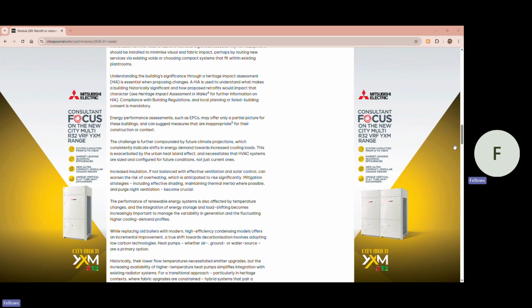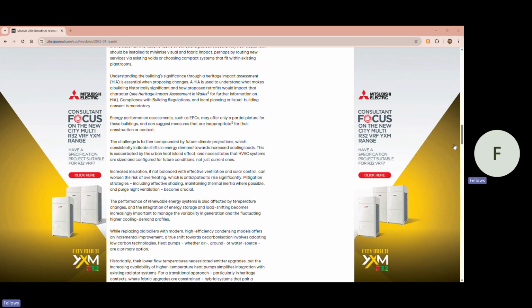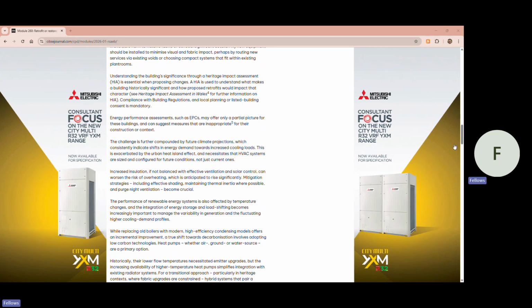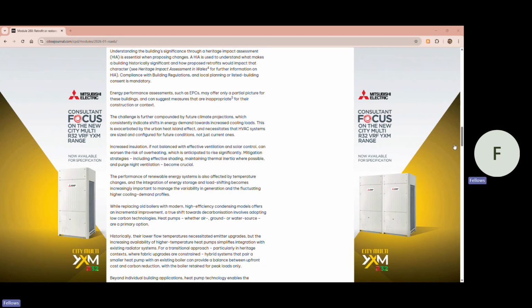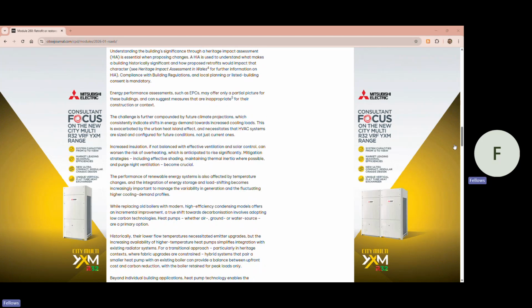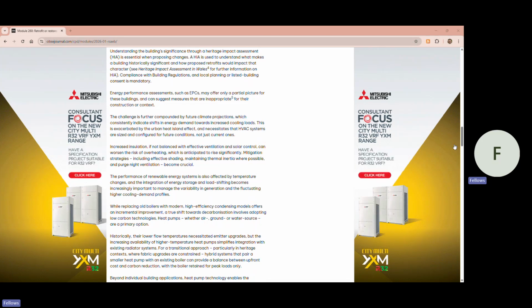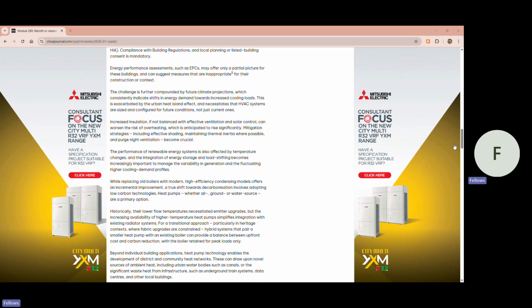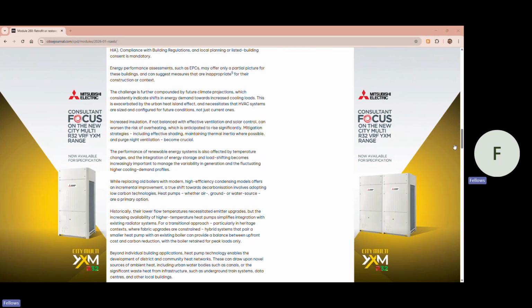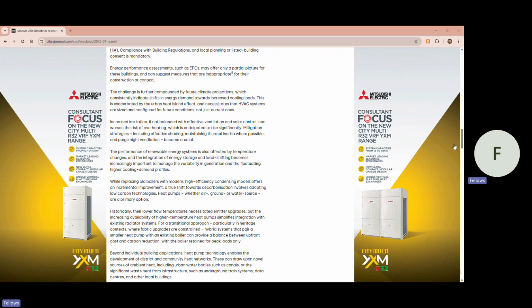This is exacerbated by the urban heat island effect and necessitates that HVAC systems are sized and configured for future conditions, not just current ones. Increased insulation, if not balanced with effective ventilation and solar control, can worsen the risk of overheating, which is anticipated to rise significantly. Mitigation strategies, including effective shading, maintaining thermal inertia where possible, and purge night ventilation, become crucial.